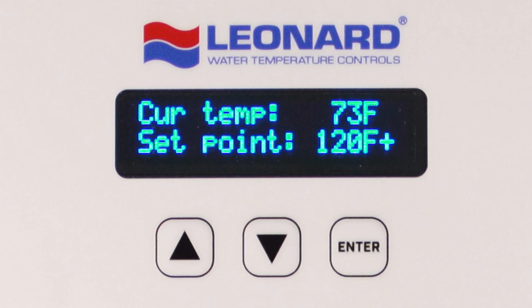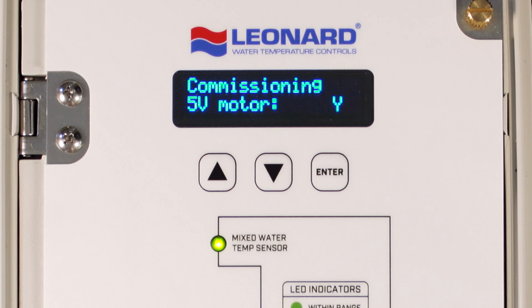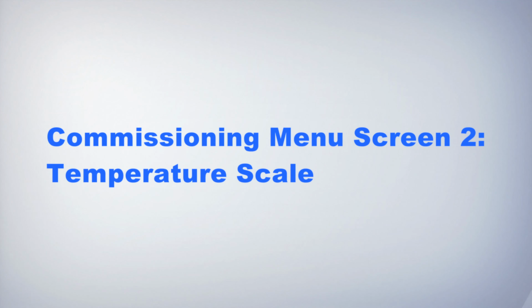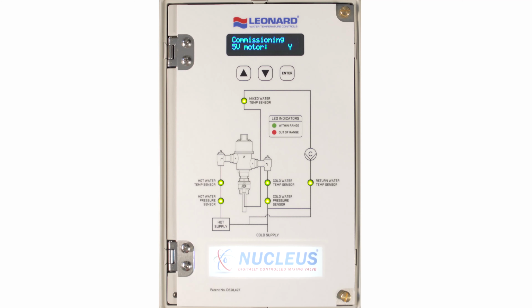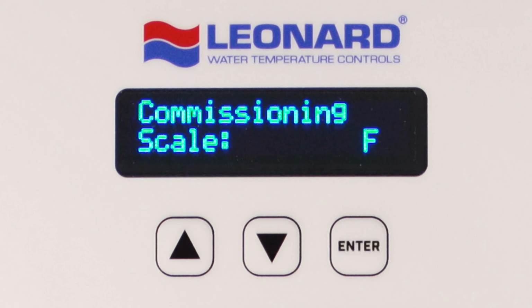The initial screen in the commissioning menu is asking whether or not the motor installed is a 5-volt motor. If the motor is 5 volts, choose yes. If the motor installed is a 12-volt, select no. The majority of motors supplied are 5 volts. Commissioning menu screen 2, temperature scale. Pressing down one time displays temperature scale. This menu requests the scale of temperature measurement in F, Fahrenheit, or C, Celsius.